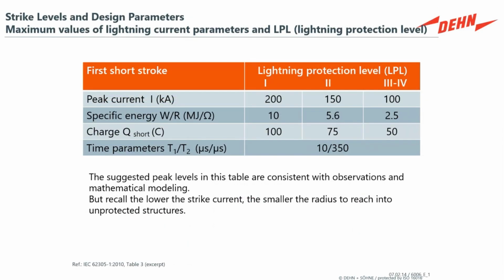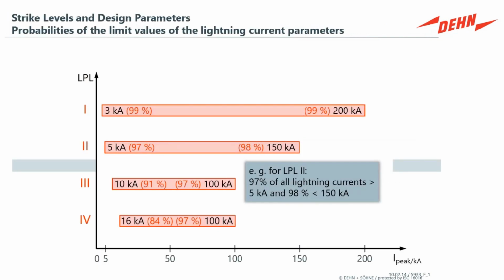And this is just a slide I like to use to describe the lightning protection mathematical parameters. So lightning is charge moving through the atmosphere. It has a charge content. It has specific energy. It has a peak current that's provoked by this charge moving through the atmosphere. It has essentially a timestamp, a fingerprint of what the lightning peak rise time and decay time looks like. And the IEC standard gives you the mathematical principles to use for calculations. Is the lightning surge protection adequate to withstand the risk category? So in our calculation methods, we assign a level of risk that we want to control. And if you have high risk, you put more measures of protection. And what it might look like is more lightning rods and more grounding and more surge protection devices.